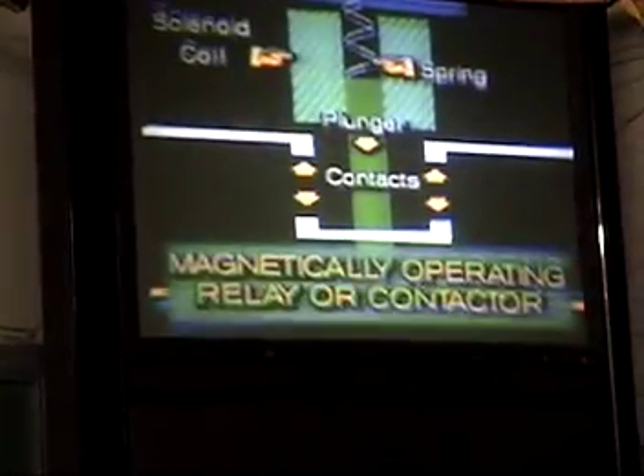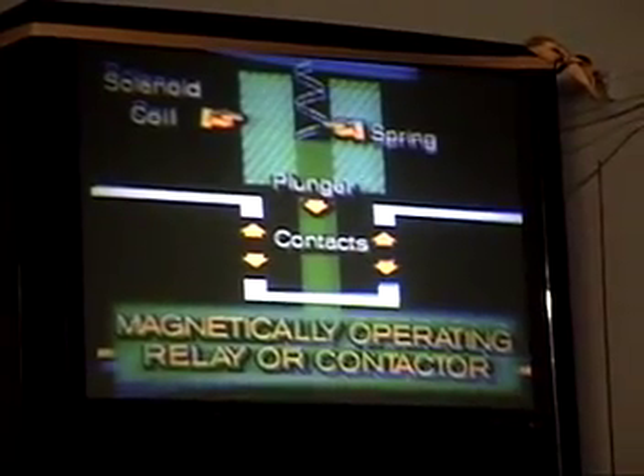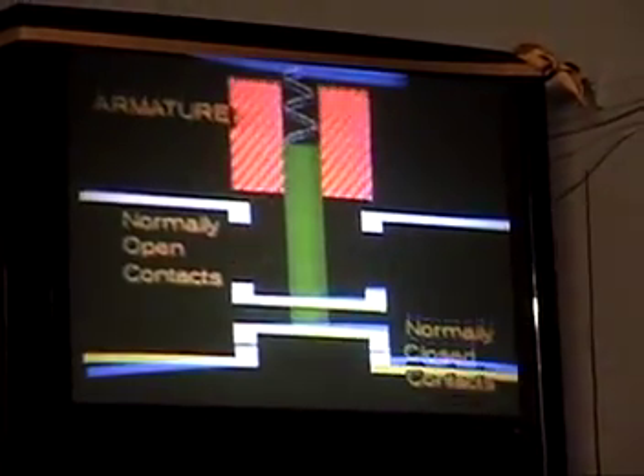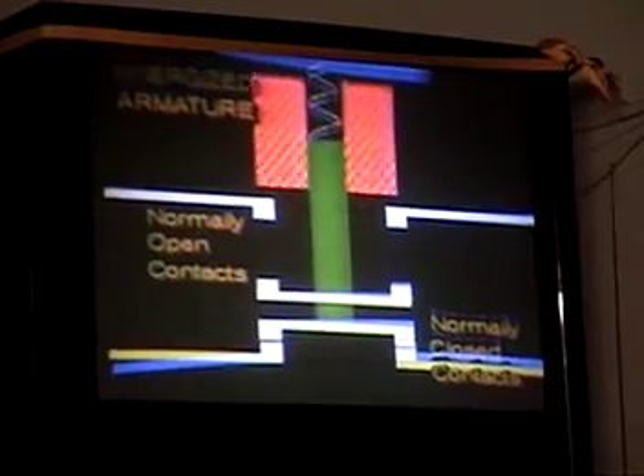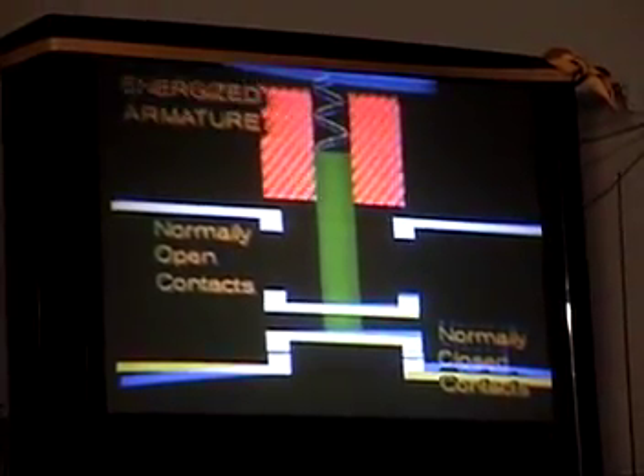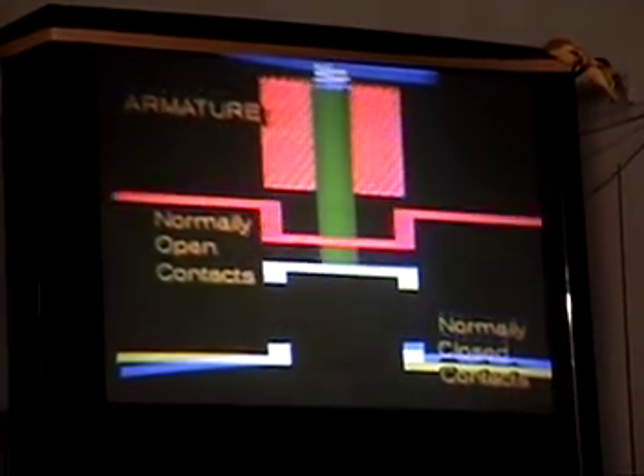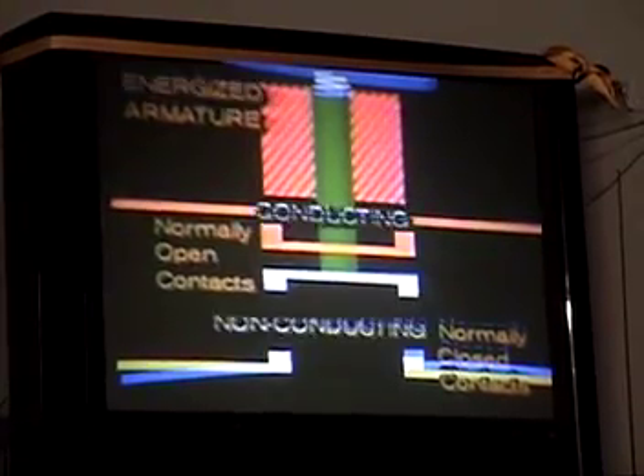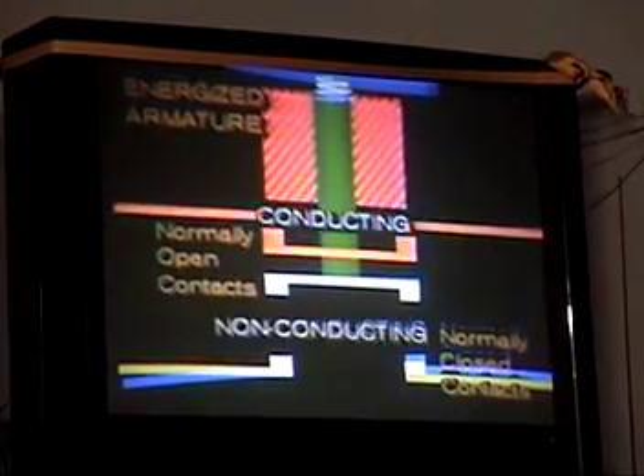The means of control in a circuit usually is a magnetically operated relay or contactor. When the coil is energized, it generates a magnetic field which pulls the armature toward the coil. The contacts will either open or close the circuit, depending on... Okay, they're kind of like showing you a contactor here. The armature at the top, when it gets electricity, it makes a magnet and boop, it closes, right?